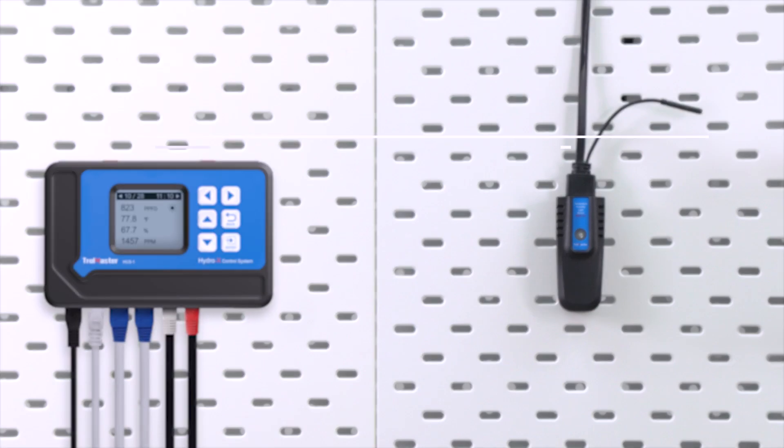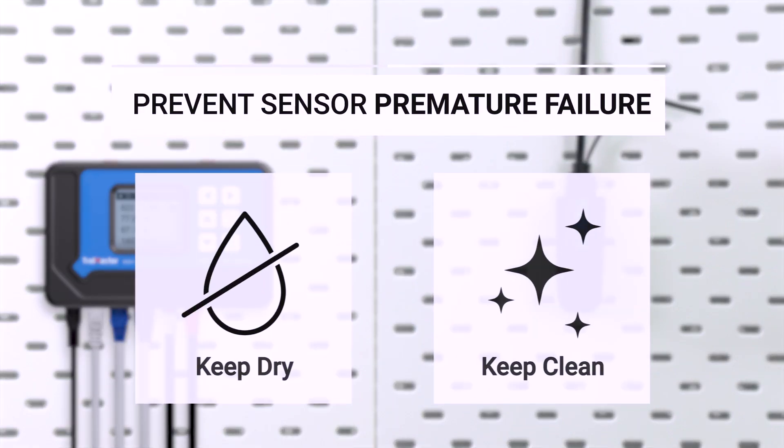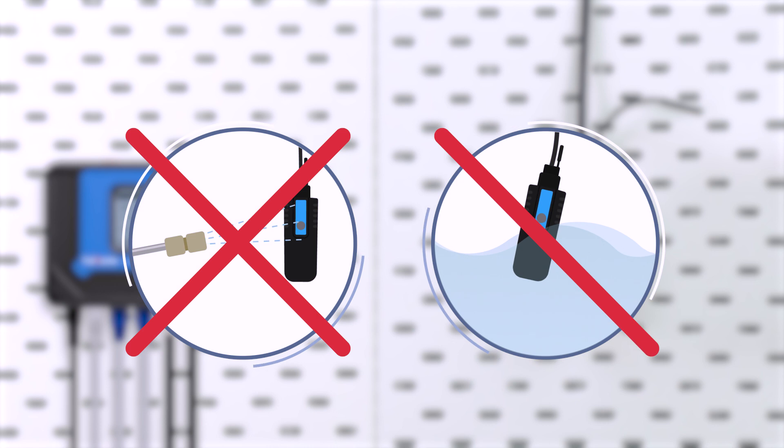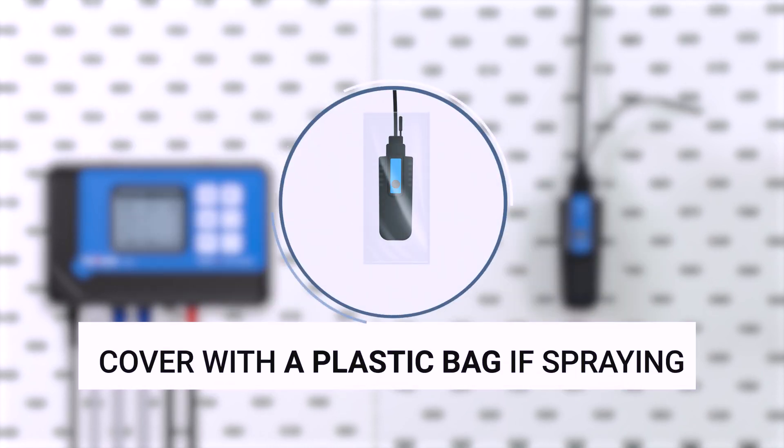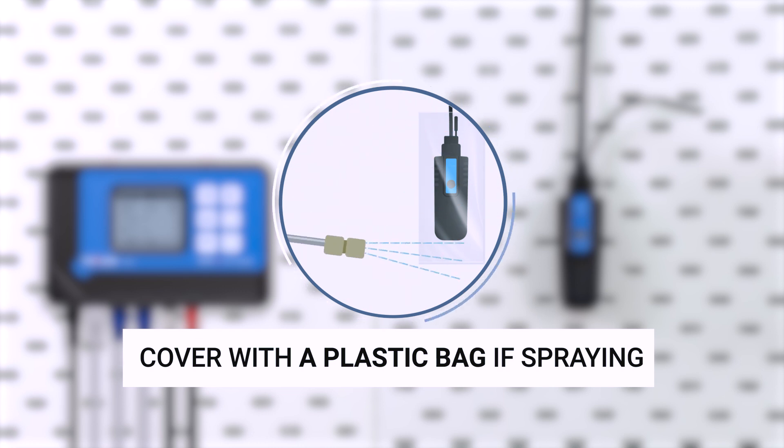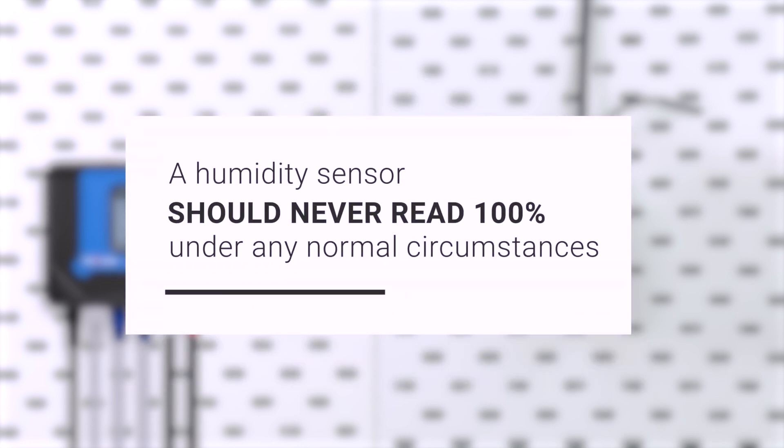The sensor should always remain dry and clean to prevent premature failure. Never spray any foreign substance or allow water or condensate on the sensors. Make sure to cover them with a plastic bag before spraying. A humidity sensor should never read 100% under any normal circumstances.